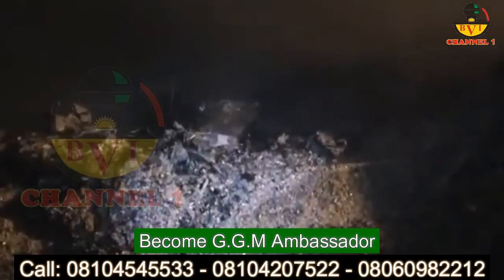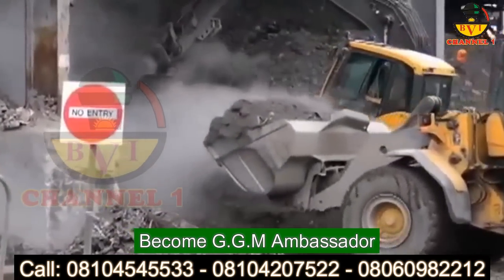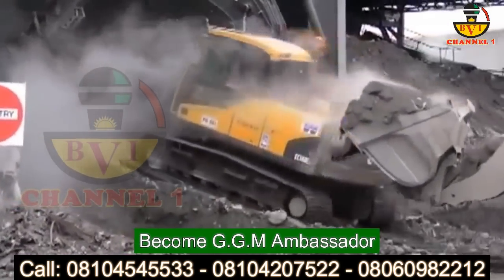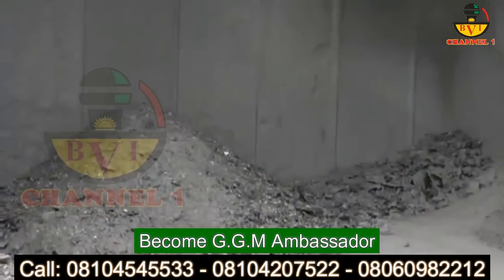The temperature in the furnace is very high. The gases in it are heated to over 850 degrees for at least 2 seconds to make sure all the waste gets burned completely to form stable end products. The residue left behind is called bottom ash and is non-hazardous. It's usually sent for recycling and is often used by the construction industry. Around 20% by weight of the waste ends up as bottom ash.